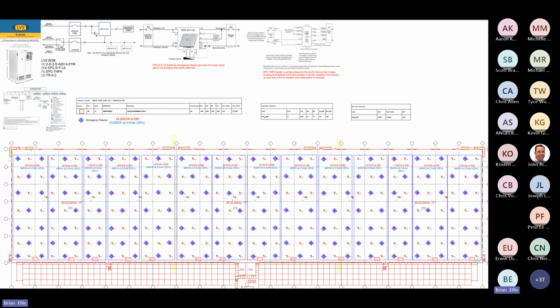And in this application, we were using a lighting control system where when it lost utility power on this three-phase device, this opened the connection so that the main hub that was outputting that beacon stopped outputting the beacon, and all the fixtures understood they were in emergency mode and they locked on. So all of our emergency lighting would be on and all reduced light output to 25% in this circumstance. So how does this pencil out?